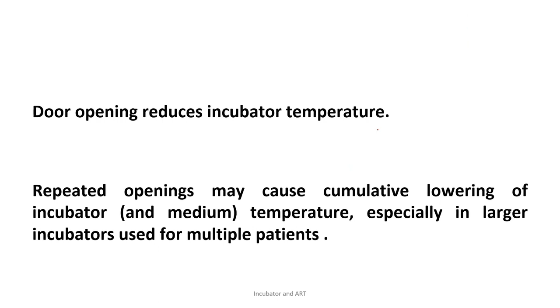So remember that when you open the door of the incubator, the hot air will come out, CO2 will fall down, alkalosis, and the temperature will drop, with hot air going out and cold air rushing in. Steam will always evaporate. So when you open an incubator, hot air will flow out, the cold air will be sucked in, and the temperature of the incubator is going to fall.